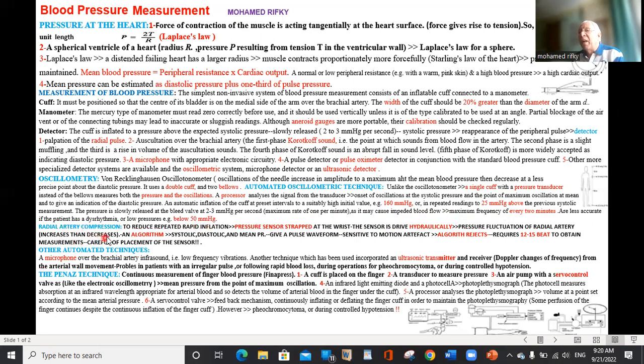Radial artery compression device is something like a pressure sensor strapped on the wrist, and then it increases hydraulically. The pressure sensor is driven by a hydraulic mechanism, increasing the pressure over the radial artery, compressing the radial artery. And this fluctuation of the radial artery by an algorithm can estimate the diastolic and the systolic and so forth. And it gives a pulse waveform. And it's very sensitive to motor artifact. The algorithm also can dismiss this artifact. And it requires only 12 to 15 beats to obtain a measurement. Of course, we must carefully place the sensor over the radial artery.